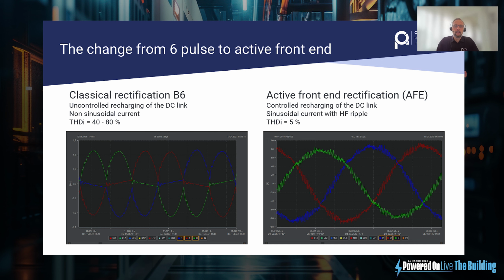And why do we need these devices? Well, if we look here on the left-hand side, this would be something like a VSD or EV charger, B6 bridge, and it has harmonic distortion. So you can see the waveform is not a sine wave. It's kind of like a double hump. On the right-hand side, you have what we call low harmonic solutions. So AFE, active front end. You can get those in EV chargers, I believe, and also in variable speed drives.